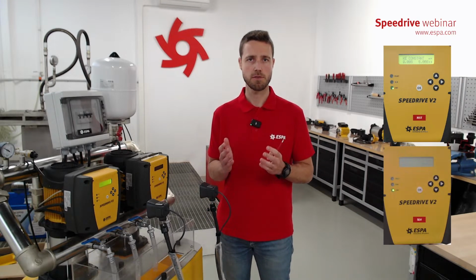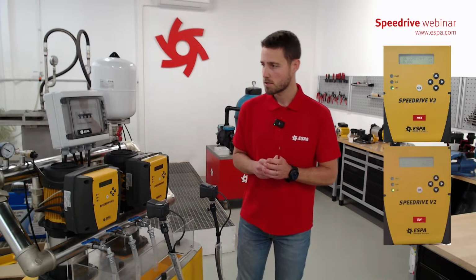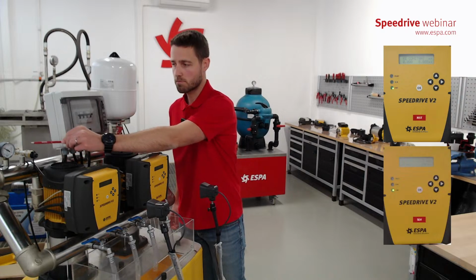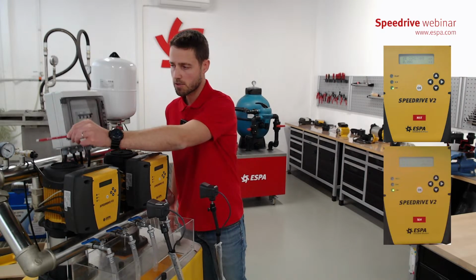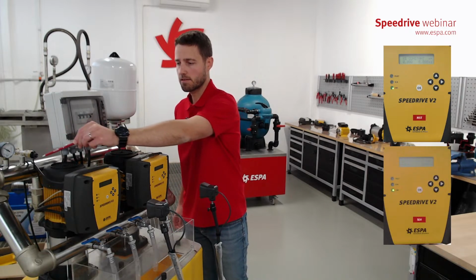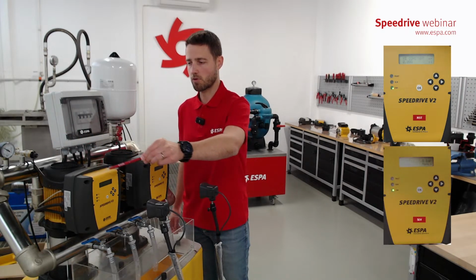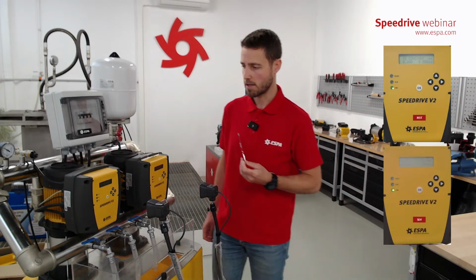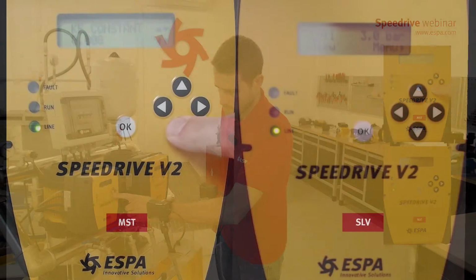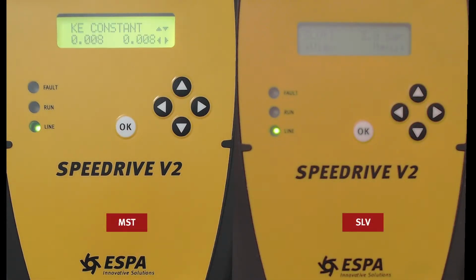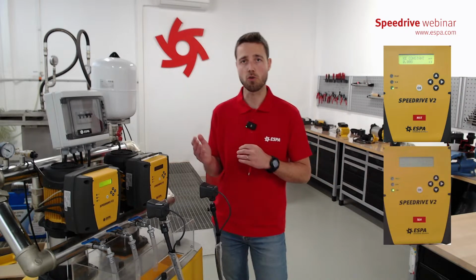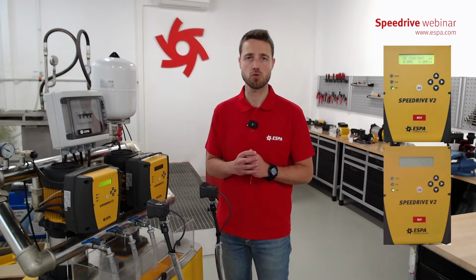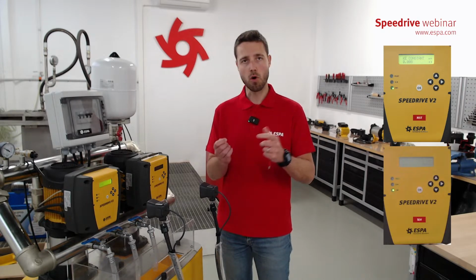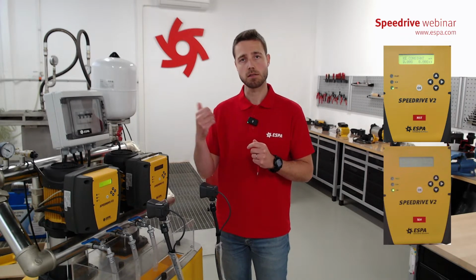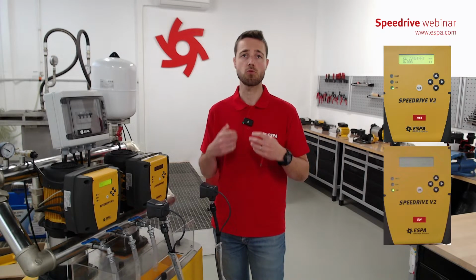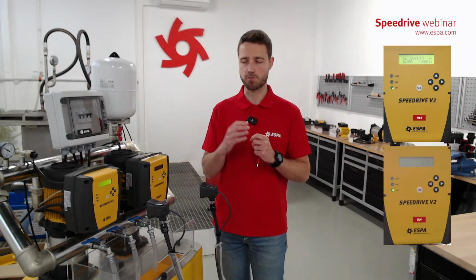But how does the VFD know that we have 3 bars? Thanks to the pressure transducer, placed over here. This part sends electrical information to the speed drives, so to say, and reads the pressure in the system. So, for example, if there is no pressure in the installation, the pumps will increase the speed. The more flow we have, the pressure will go down, the transducer will detect this loss of pressure and will communicate to the speed drive to increase the speed.